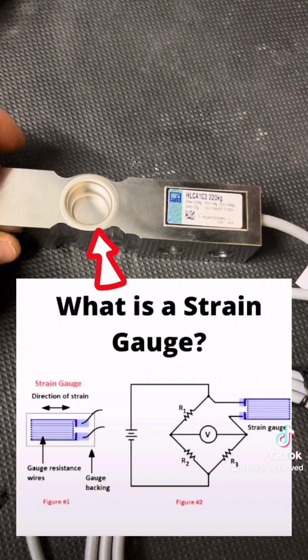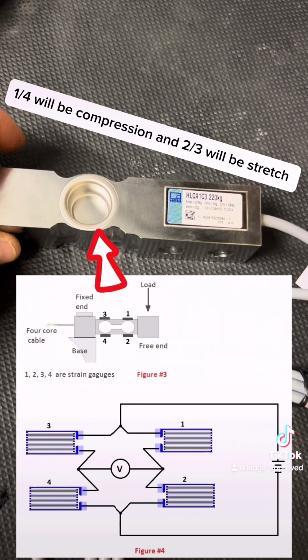These output changes can be so small that that's why we have to put it into a Wheatstone bridge circuit. So the basics of a Wheatstone bridge I'll go into, but if anybody wants me to do a more detailed video, I can do, but that'll be a whole video. But the basics of it, the Wheatstone bridge circuit converts a resistance change into a voltage change, and this amplifier makes the voltage change usable. So this is handy when you're using sensors or components which give out a very small change in resistance, such as a strain gauge or a PT100, the voltage can be converted into a voltage difference that can be read a lot easier. They can be all wired up in loads of different configurations.